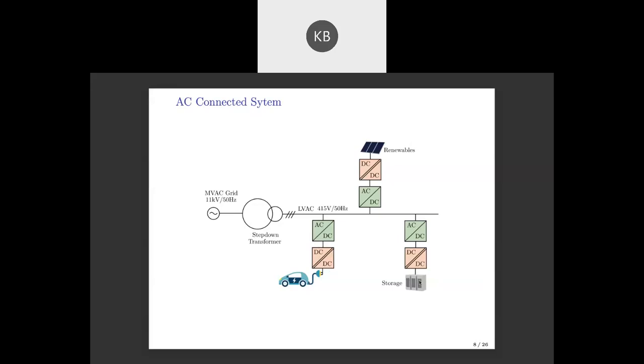The three-level inverter, T-type, neutral point clamped, or the regular two-level inverter are all bidirectional, so they can support power flow both AC to DC and DC to AC. But the DC-DC converter here has to be bidirectional, while the other DC-DC converters, as indicated, have to be only unidirectional. That's why most designs use phase shifted full bridge based converters in these two DC-DCs, and many designs use two DC-DC converters, one in each direction.